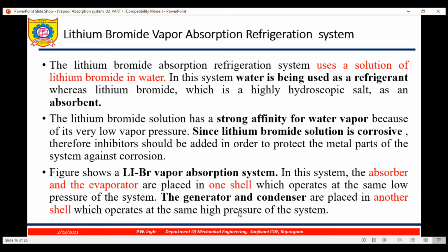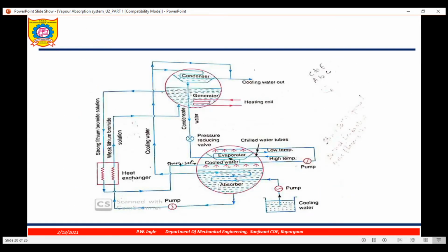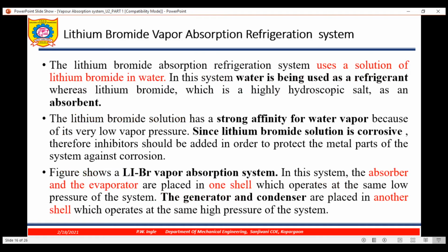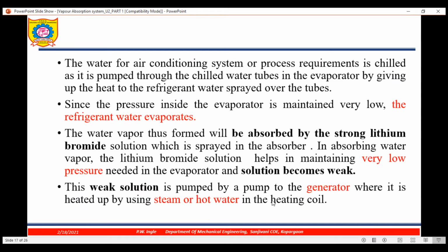In this system, the absorber and evaporator are placed in one shell, and the generator and condenser are placed in another shell, which operates at a high pressure. The evaporator and absorber operate at low pressure. Same low pressure means that in the evaporator and absorber the pressure is the same. Similarly, in the generator and condenser the pressures are the same.